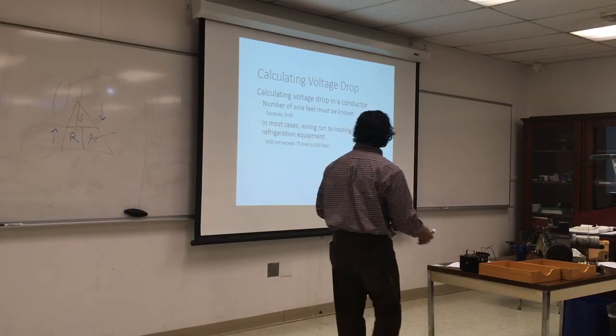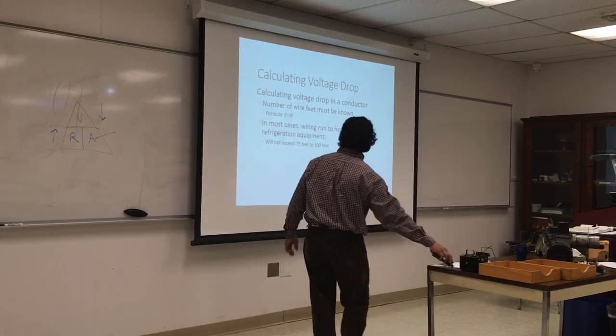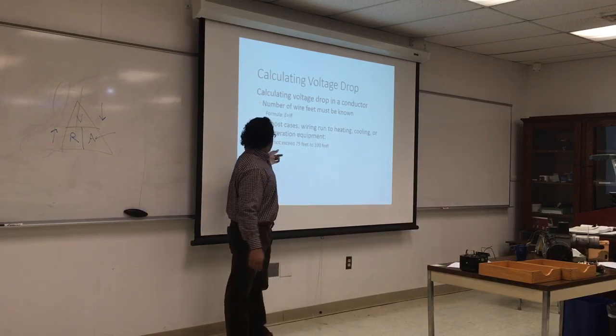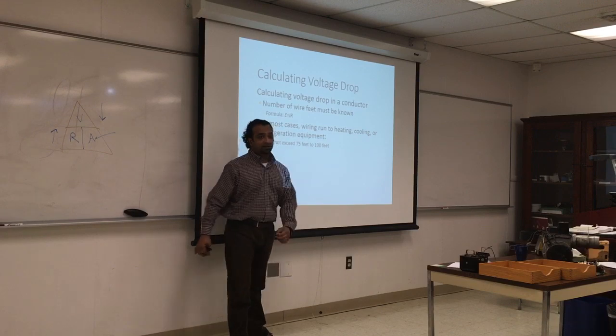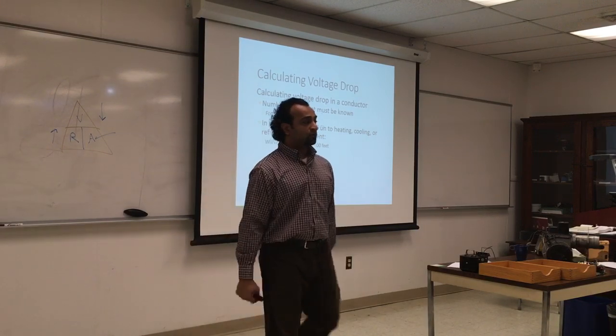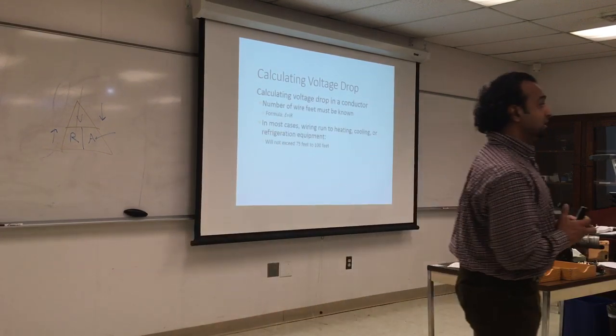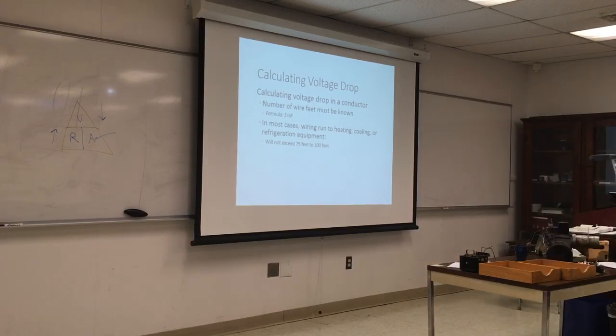Yeah, voltage drop. So usually, okay, it's feet and meters. You will not exceed 75 or 100 feet from the source of the power. And again, that will be in the installation guidelines. It will tell you, okay, this equipment was sized and designed to be 100 feet from the main source of power. So you'll go measure the main source. Again, the main source is probably a few feet away from the control panel. So you always measure the voltage drop.